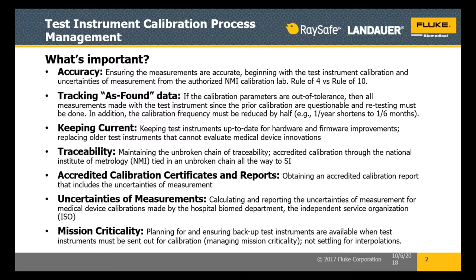The accuracy of the measurement is critical, especially if we're looking at something delivering medication — an infusion pump, for example. The same infusion pump that may deliver D5 and water or normal saline with a little bit of medication to a patient in pretty good shape may, half an hour later, be delivering chemotherapy to a cancer patient. If I'm that cancer patient, I need that device to be accurate. I do not want an overdose of that chemo — it's already making my hair fall out and making me sick. Sometimes it's good to walk in the shoes of the person you need to protect most: the patient.